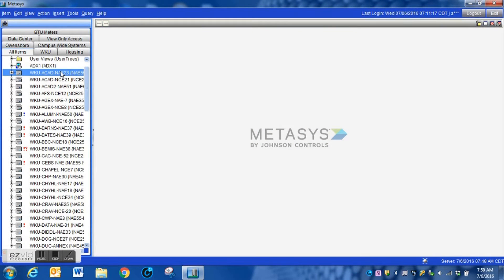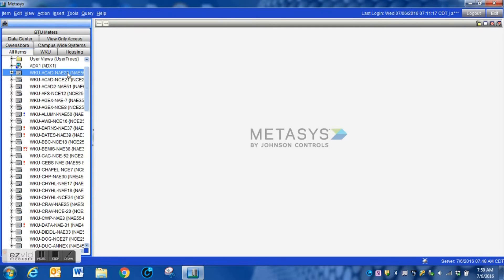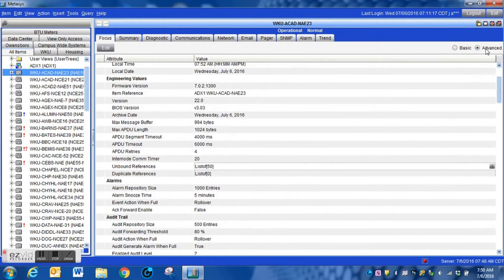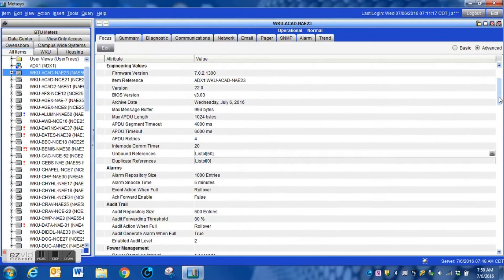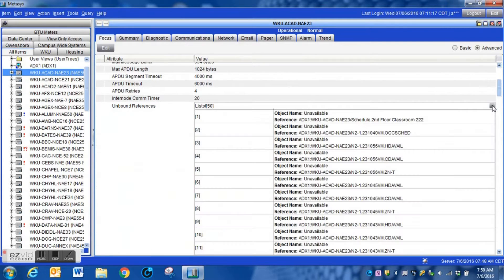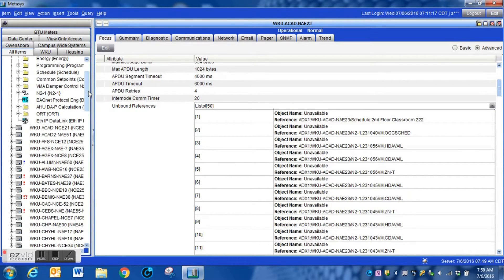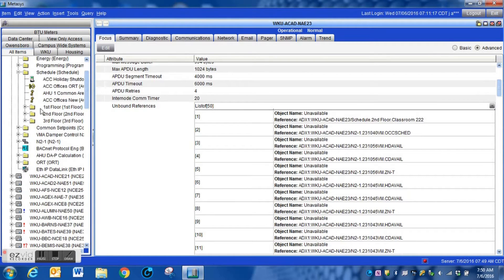Looking at your network map under Metasys, you should see all of the NAEs on your system. To view the unbound references pool, pull one of the devices over into your view window. Under the Focus tab you will see a display section labeled "Unbound References." If you drop that tab down, you will get an entire list of all the reference points inside that NAE that cannot be found.